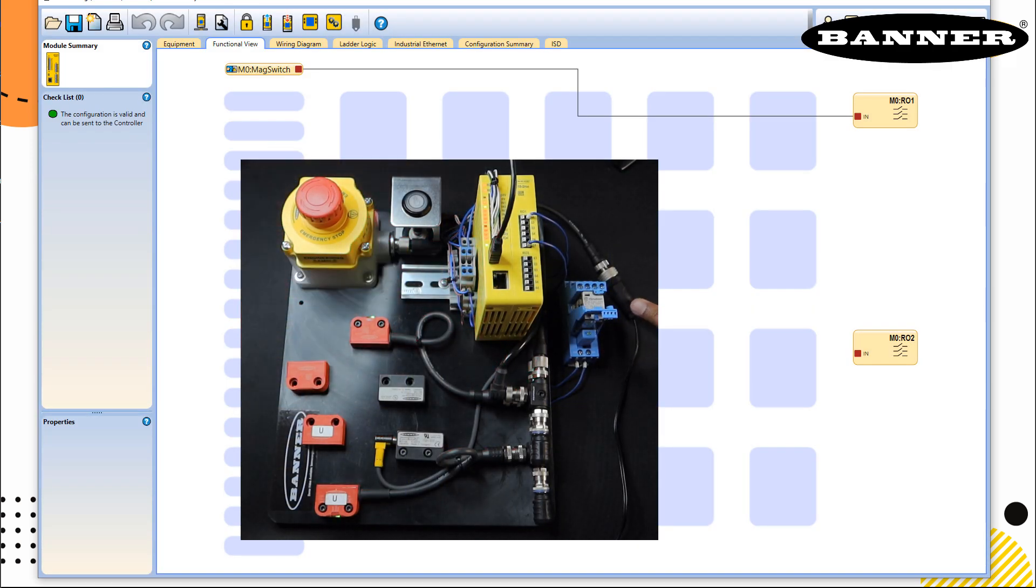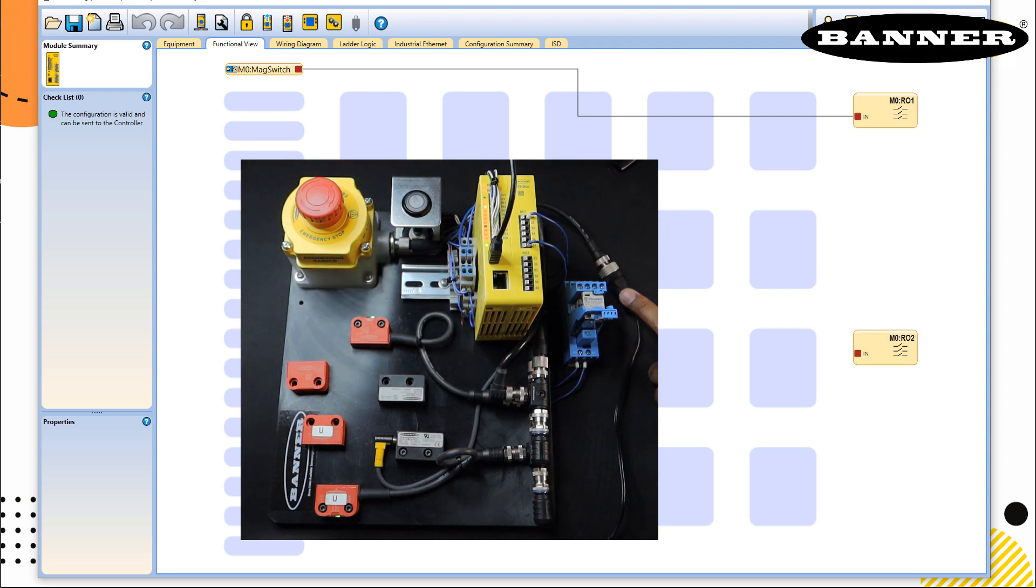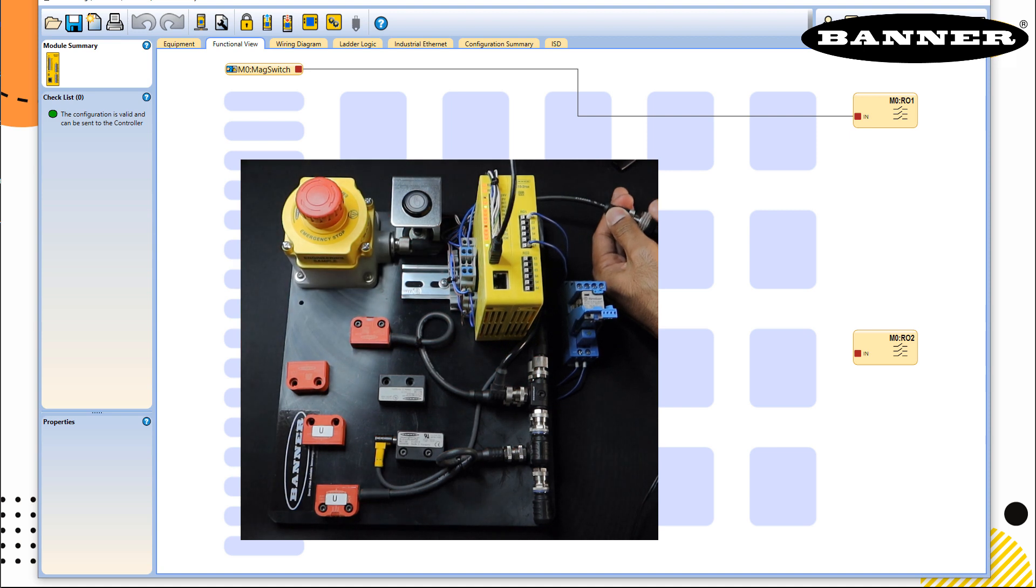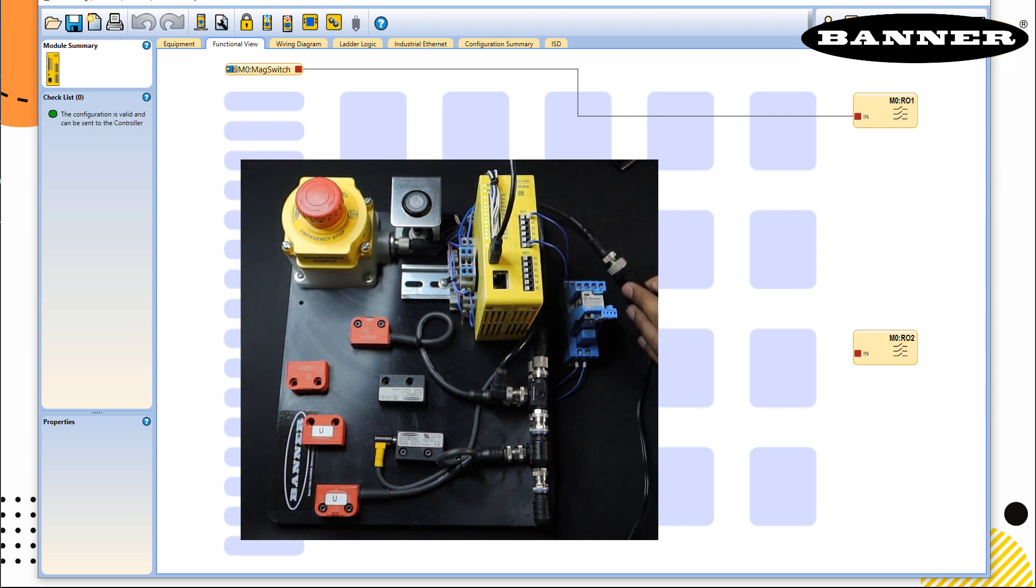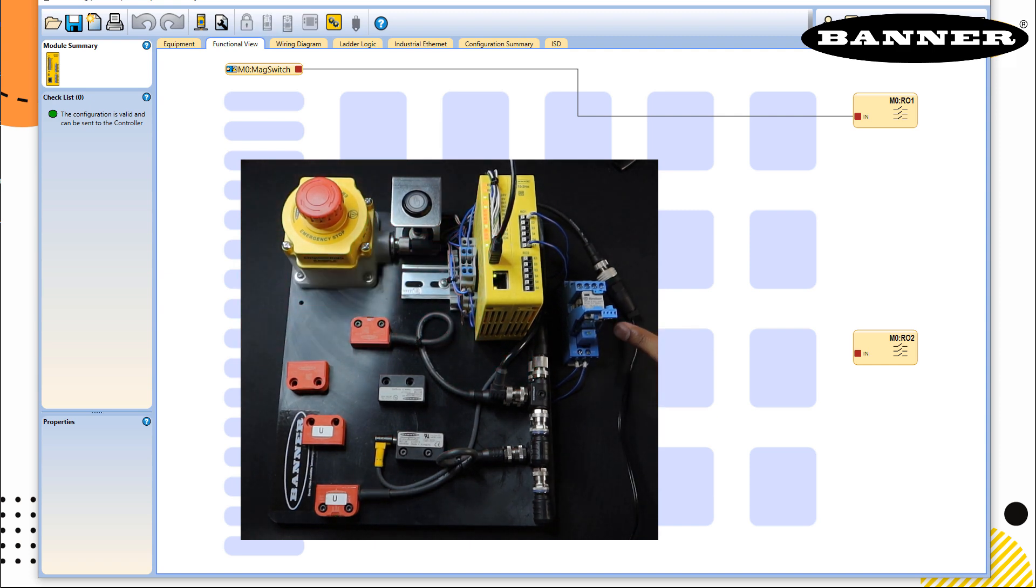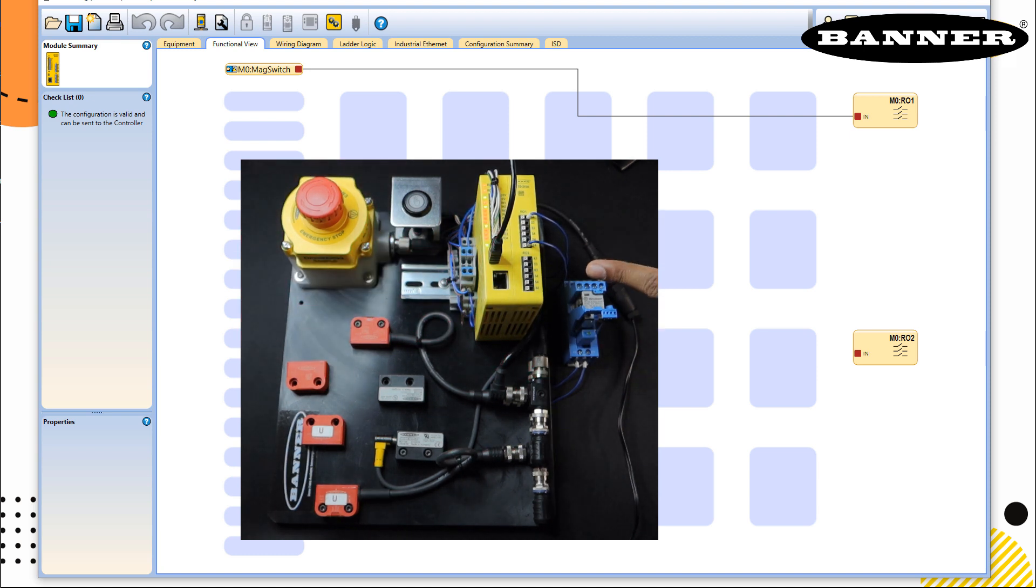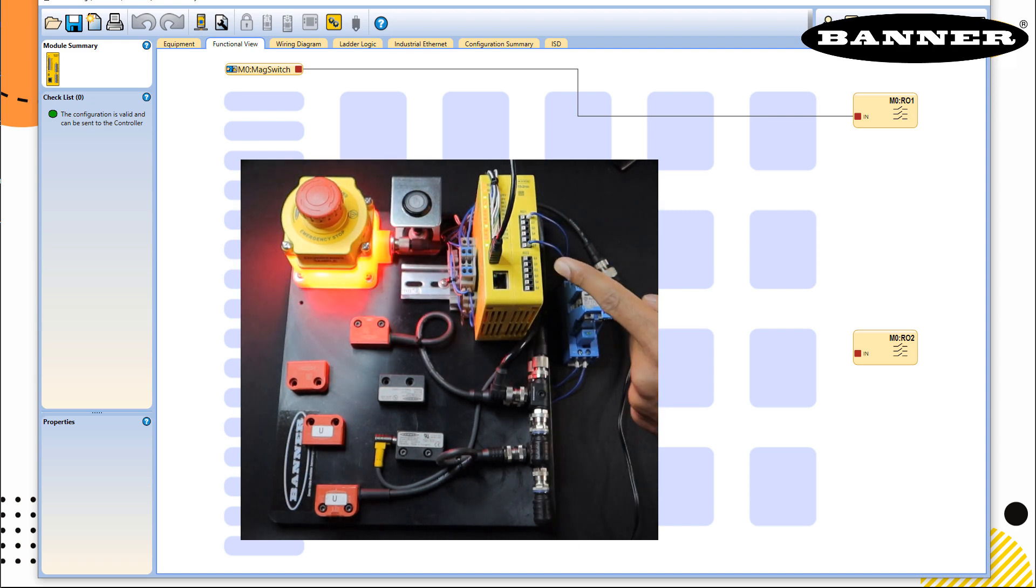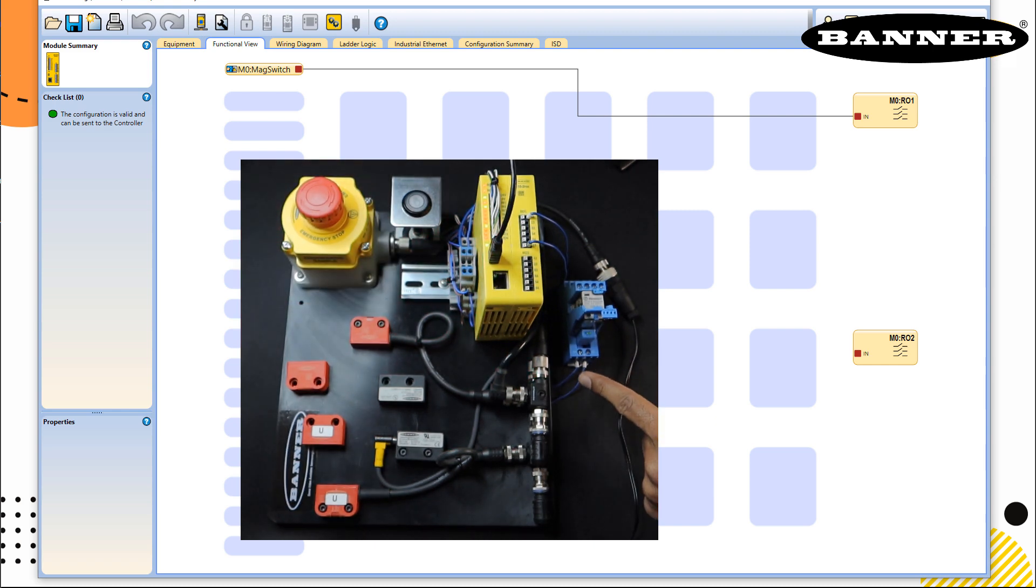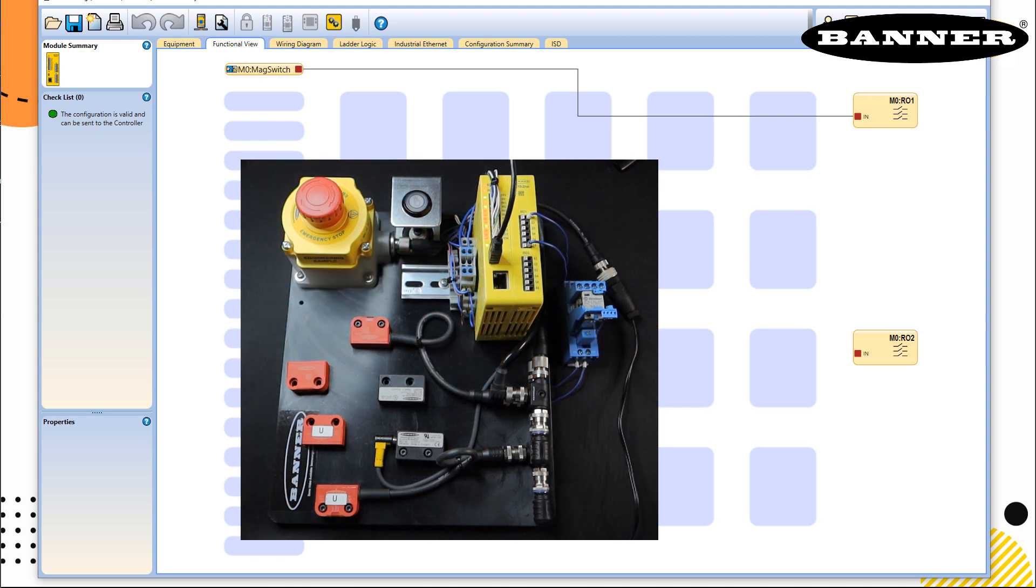In this case, I will just turn off the power supply from this cable. And so I will just unplug it and plug it again. So this will turn off the controller because 24 volt is gone, and then plug it again. Now I have added an extra relay here. So if you notice here, this relay is connected to my terminal number 13 and 14. So 13 and 14 is my NO contact. So to 13 I have provided 24 volts, 14 is going to the relay coil and it's getting zero volt directly. So in this case, if my RO1 is true, the relay will also get true.